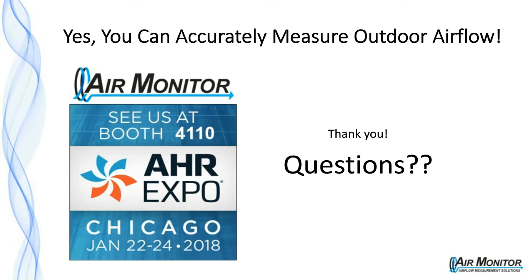Absolutely, Barry. I'll read the whole thing here. It says, using a mesh would involve contamination from poplar fluff, etc., and would require cleaning on a regular basis. It would also provide erroneous readings when it is contaminated. I'm not sure if it's a rain hood or if there's no louver available. If there's a louver, obviously the louver can be used. But in most outside air applications, especially when you have this type of seasonal contamination, you also have bird screen on these inlets. And that bird screen will end up getting contaminated too. So I don't think we're inducing any additional maintenance beyond what's already going to be required for that type of regional and seasonal contamination. But it's not going to affect the accuracy or the performance measurement of the system.